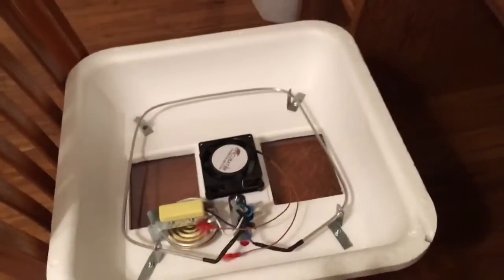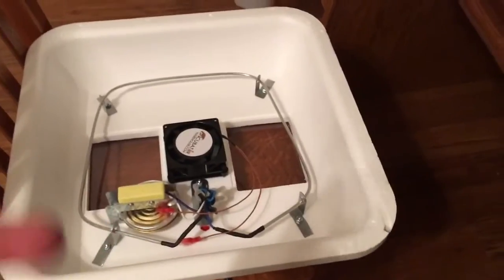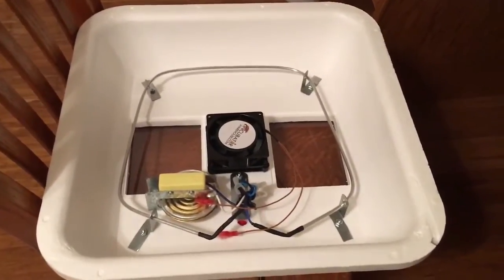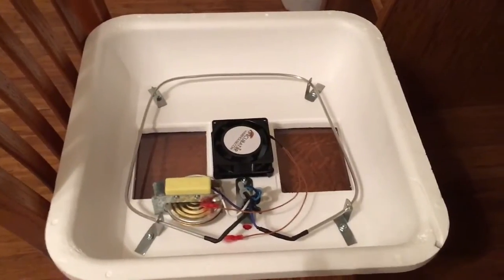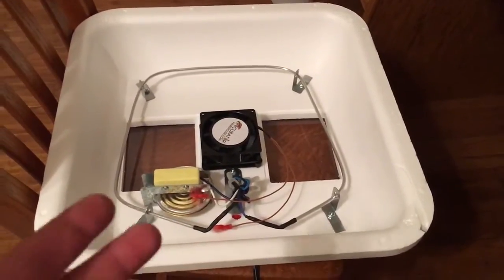What it's actually got is there's a screw right there, whoopsie, I guess it's the second screw, down there closer to the red on the bottom. And the hole is already pre-drilled in the lid because if you don't have the circulating air kit, those holes are already in the lid to help get just general air flow. So holes are already there.